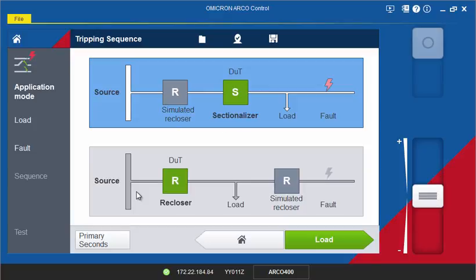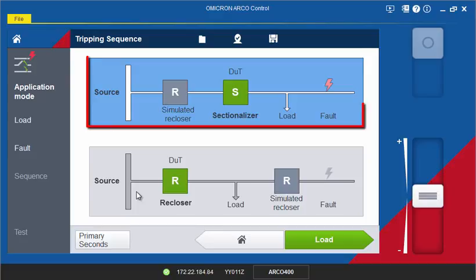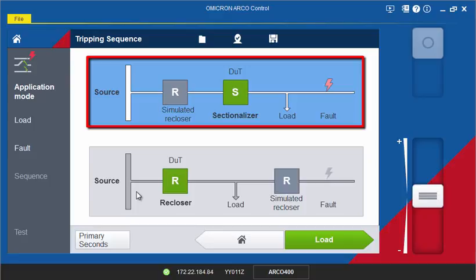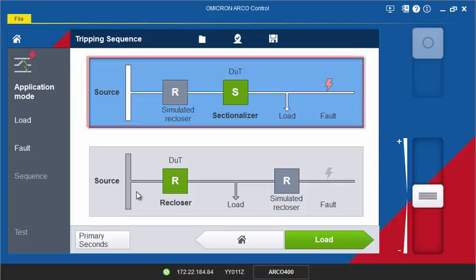The tool offers two modes for testing. Select the Sectionalizer mode if you are testing a Sectionalizer control. In this mode, the software will simulate an upstream recloser in order to test the counting increment of the open sequence to lockout of a Sectionalizer control.